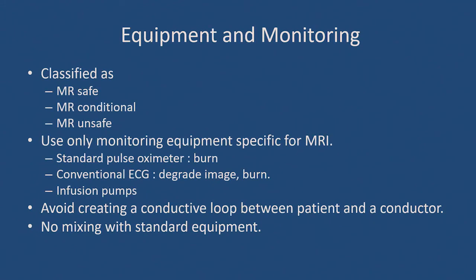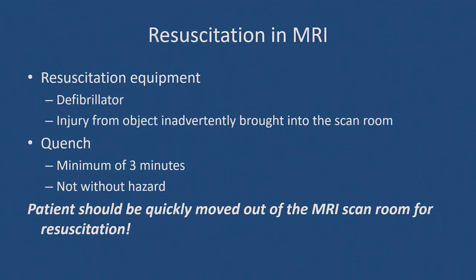Patient equipment are classified as MR safe, conditional, or unsafe. Equipment brought to the MRI venue should be MRI compatible to avoid burn injury to patients. In case of the need to resuscitate, patient should be quickly moved out of the MRI scan room.